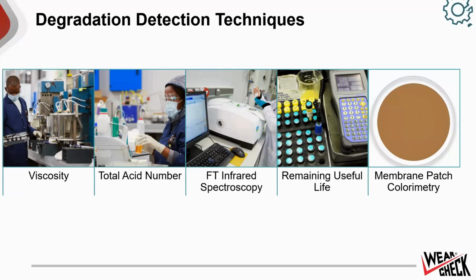Then you have infrared analysis. This one is often called the oil's fingerprint, because it uses infrared light to detect oxidation by identifying chemical changes in the base oil. So it basically shows how oxidation changes the hydrocarbon backbone of the oil into different types of byproducts. And it's those byproducts that we can measure using infrared spectroscopy.